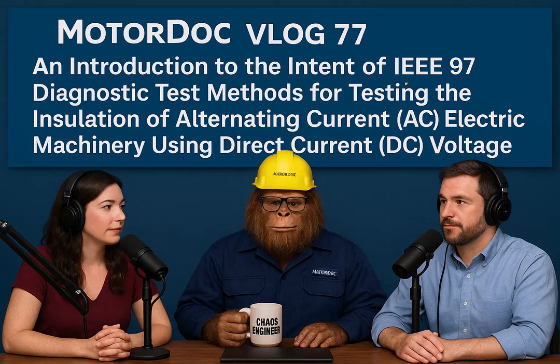Well, the guide details how they can help pinpoint things like thermal degradation, that's just basic aging from heat, electrical degradation, so damage from voltage stress. Right. Problems if the insulation wasn't, say, fully cured properly, degradation of the stress control coating. That may be voltage in the end windings. Exactly. Crucial part. Also, moisture, whether it's just sitting on the surface or if it's soaked deeper in, general contamination, dirt, oil, and even internal tape separation, delamination. Wow, that's quite a list. Covers a lot of potential failure modes.